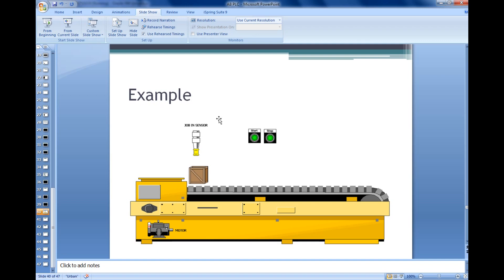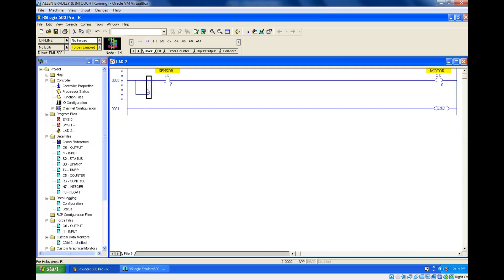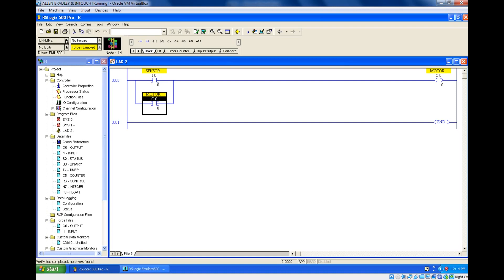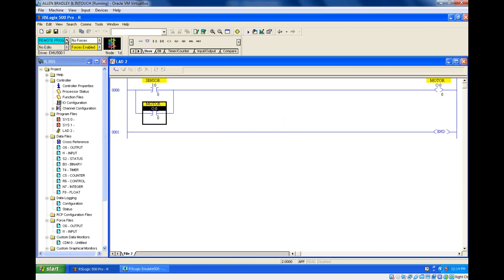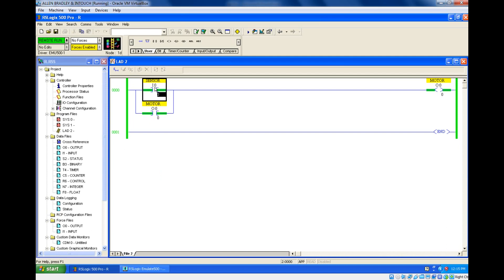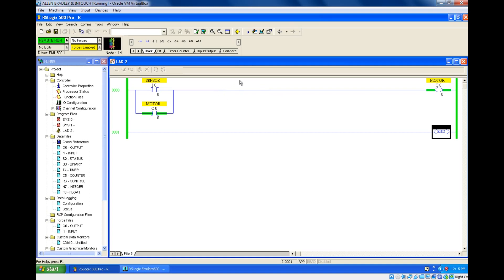The job-in sensor should not give a continuous signal because the object has moved. In this case you use the latching concept — connect a parallel contact with the sensor input and the motor output. Now even though your sensor is not giving a signal, the motor continues to run. See — your sensor gives signal, conveyor motor runs, the box moves away, sensor gives zero, but your motor is still running. To turn off the motor you use unlatching — maybe a job-out sensor detecting the object at the destination.